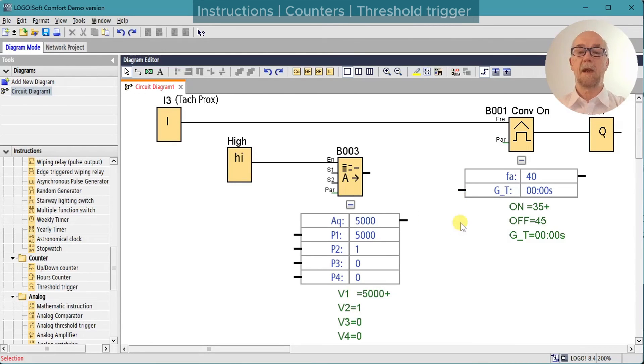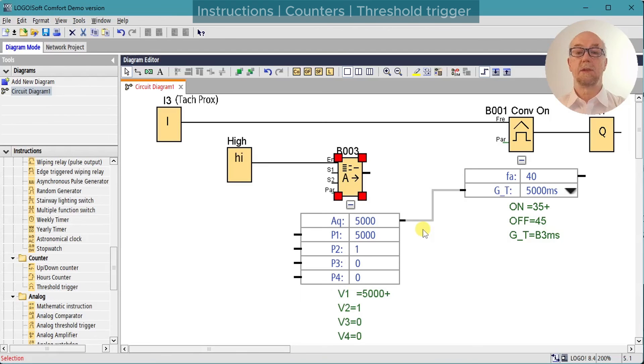To do that we can use an analog multiplexer, which allows us to select one of four values depending on the pattern of selectors S1 and S2. I've set value 1 to 5000 milliseconds and value 2 to 1 millisecond. With S1 and S2 both off we get value 1; with S2 on we get value 2. We can then feed that analog value to the gate timer — toggling S2 switches between the two values.